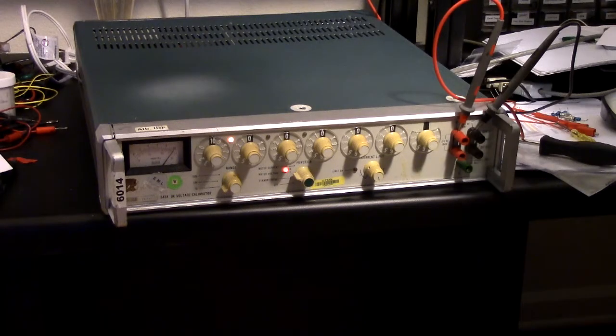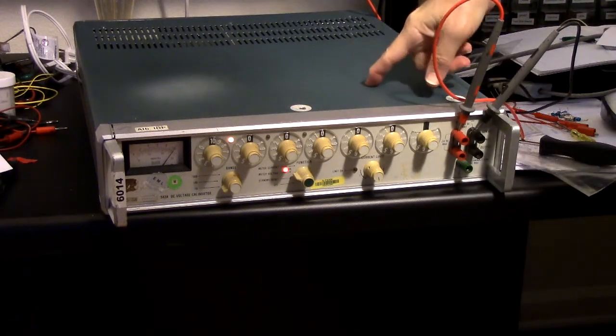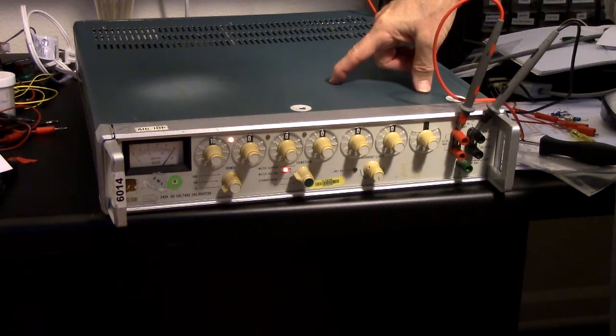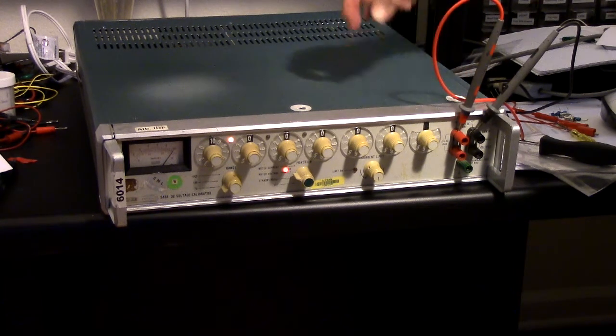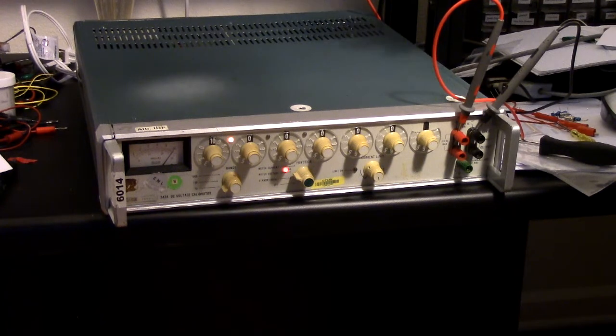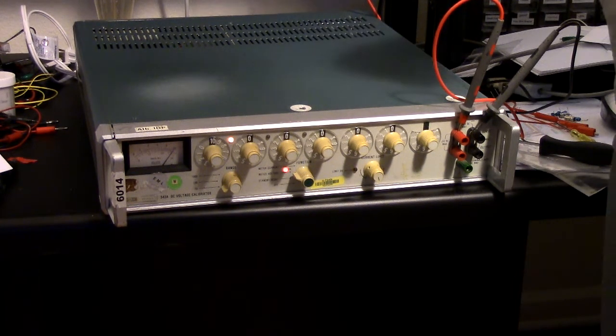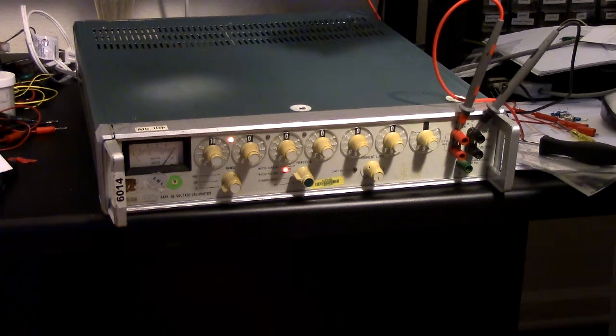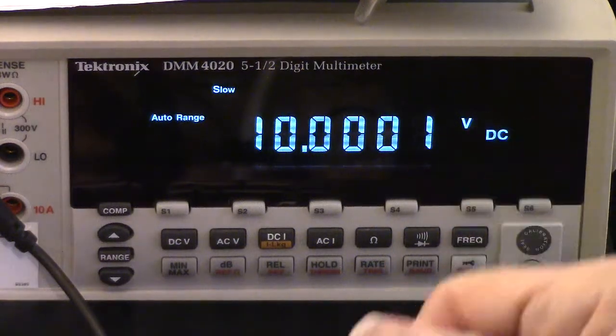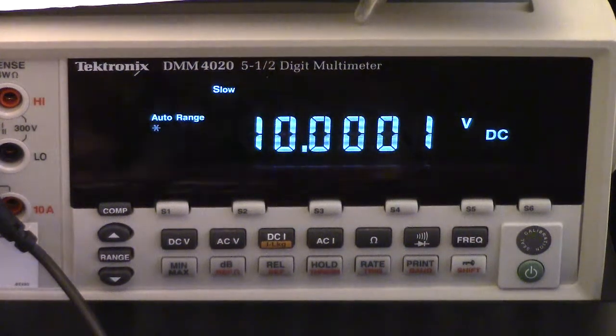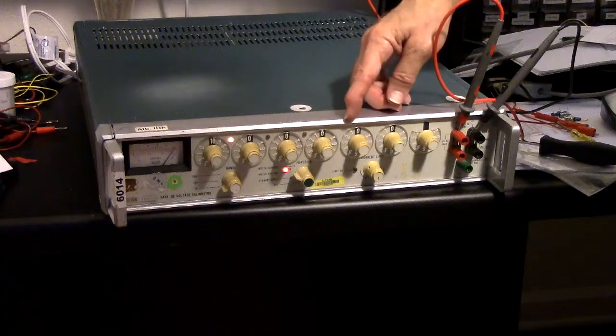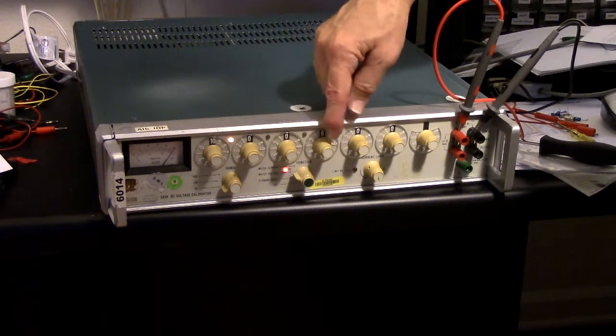So now I guess the question is, how accurate is it? Did replacing those capacitors affect the calibration? Actually, looking at the circuit, which I did once, those that I replaced really shouldn't affect the calibration. And it does seem to be pretty much spot on still. This has been operating for a while. So I've got it set to 10 volts output, 10.00000.